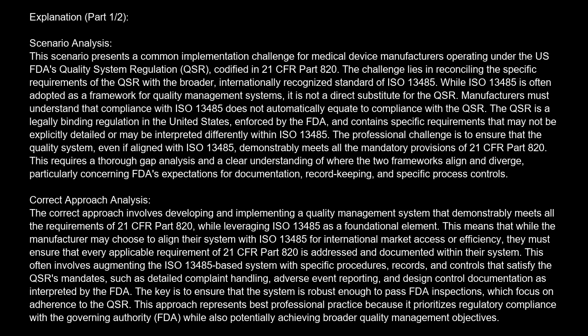While ISO 13485 is often adopted as a framework for quality management systems, it is not a direct substitute for the QSR. Manufacturers must understand that compliance with ISO 13485 does not automatically equate to compliance with the QSR. The QSR is a legally binding regulation in the United States, enforced by the FDA, and contains specific requirements that may not be explicitly detailed or may be interpreted differently within ISO 13485.